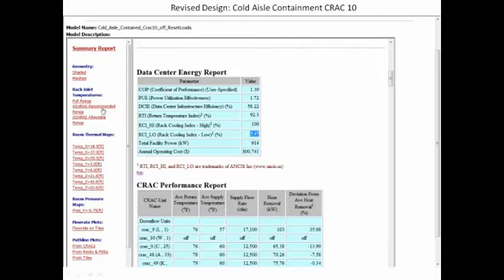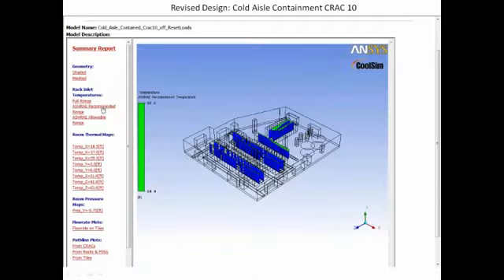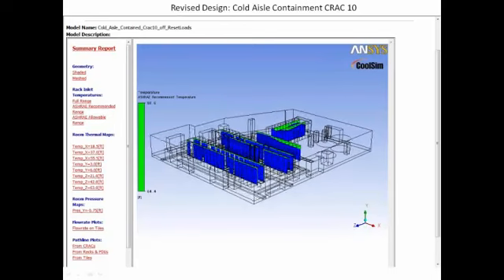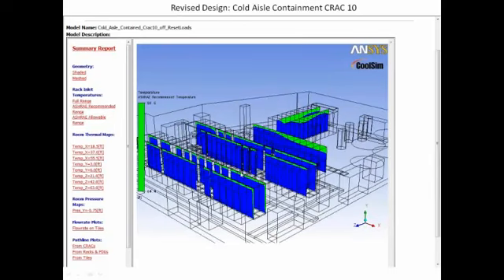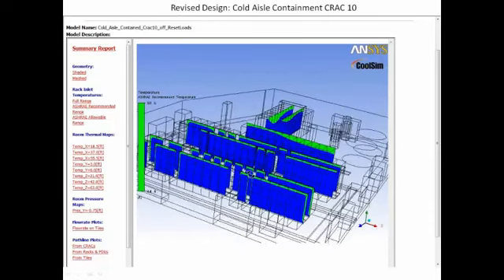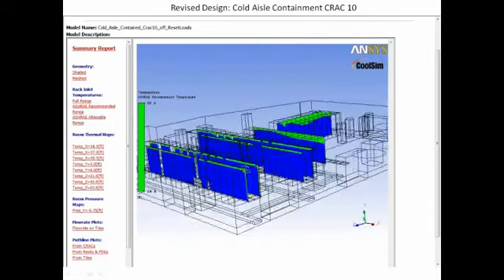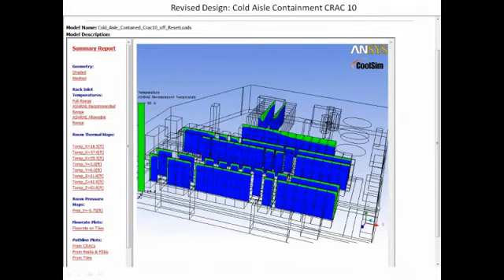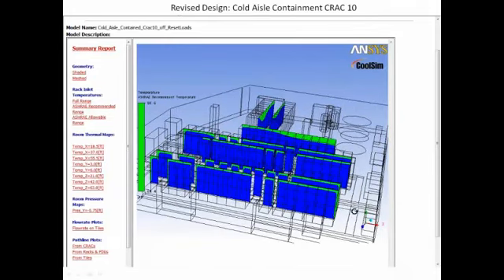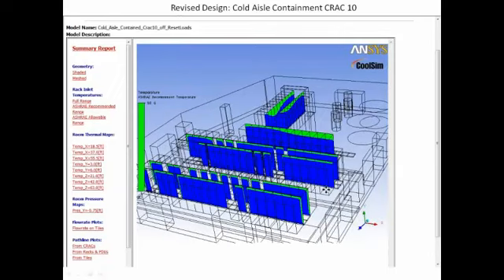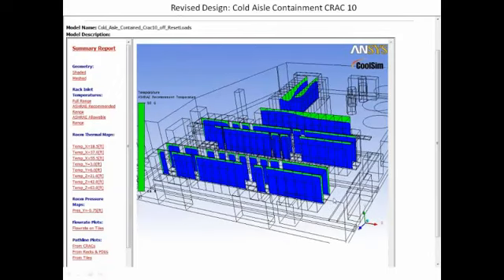If we take a look at my RCI high, which was below 100 prior, now is perfect. So I'm within range. I'm too cold still. So there's an opportunity here to begin to raise supply temperature, particularly the temperature of these cooling units down at this end of the room. We weren't able to do that before because we didn't have enough uniform temperature down here in this room to even give that a shot. But now we're running with one of the 30 tons off. Things are looking pretty good. And there's an opportunity here now with containment to begin to drive up the temperature.